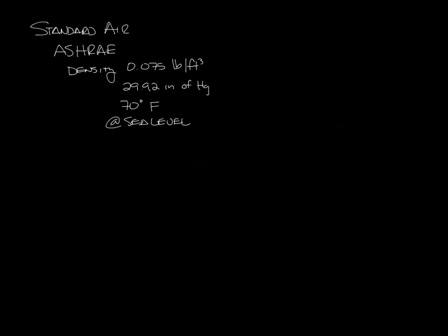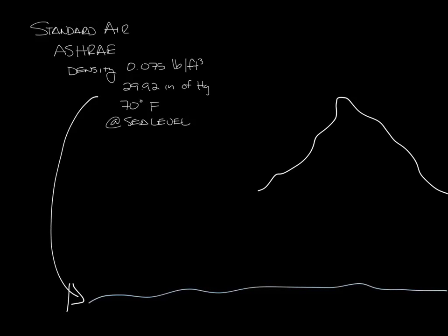So if you're operating your fan or water coil at sea level you're probably pretty close to using standard air. But if you're operating your equipment in conditions where the density is different, like at high altitudes maybe at 6,000 feet at the top of this mountain, then your performance could be off from the catalog data by quite a lot.